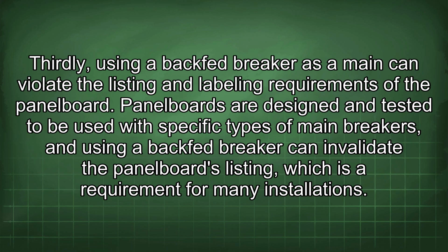Thirdly, using a backfed breaker as a main can violate the listing and labeling requirements of the panel board. Panel boards are designed and tested to be used with specific types of main breakers, and using a backfed breaker can invalidate the panel board's listing, which is a requirement for many installations.